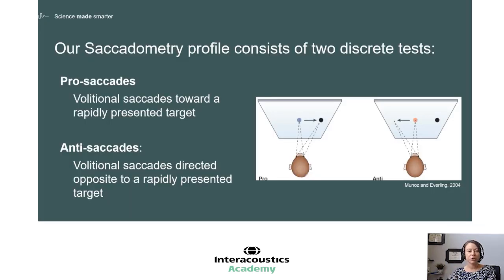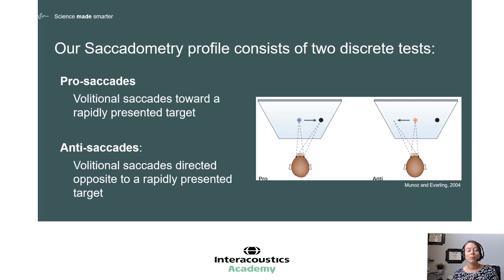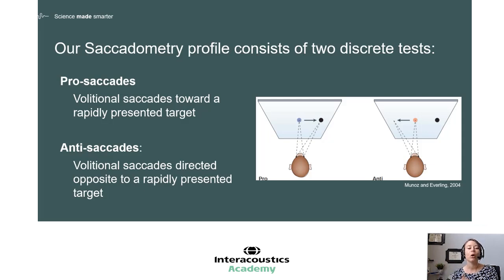Saccadometry actually consists of two subtests. The first one is called pro-saccades, and the second one is called anti-saccade. In the pro-saccade test, the patient starts looking at the center dot, and a dot pops up either to the right or to the left. Their job is to move their eyes towards the dot, which most patients do quite well at. You'll see in our graphical example that a correct pro-saccade movement has the patient starting with their eyes on the center dot, the dot moves to the right, and the patient also moves their eyes to the right.